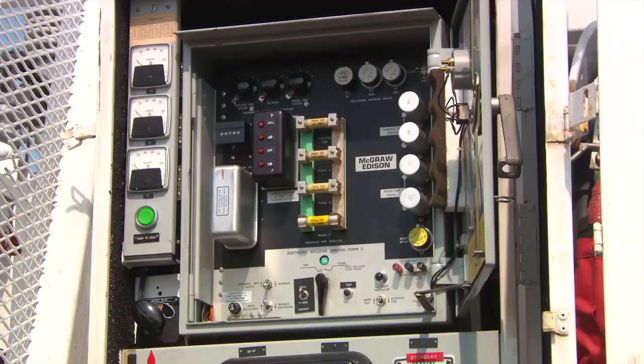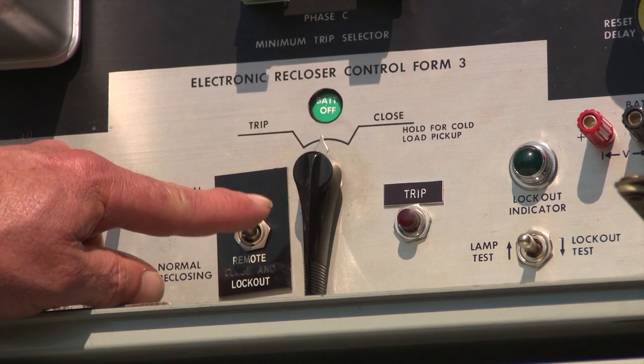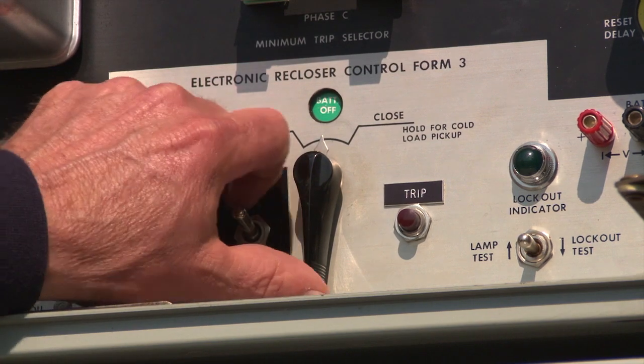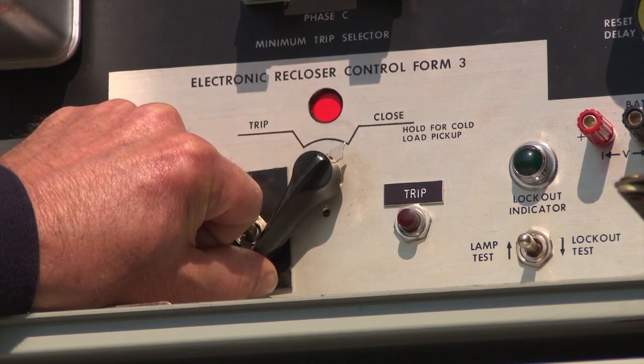VSO reclosers open on all three phases when a fault occurs. They usually have a cycle of 1 quick trip operation followed by 3 slow trip operations. On the 4th operation, they will stay open if the fault isn't cleared. The close trip switch enables closing or tripping and is used to electrically test the operation of the recloser.